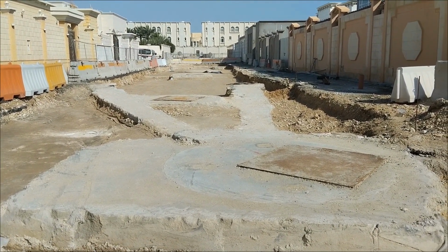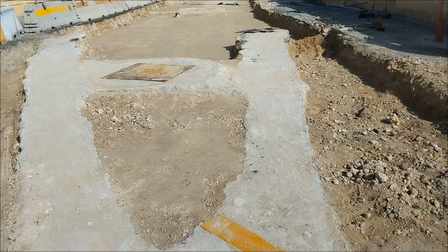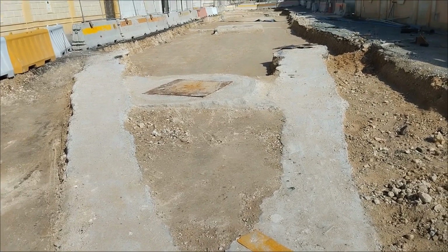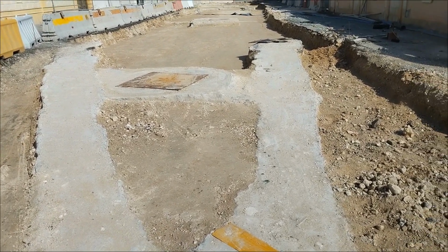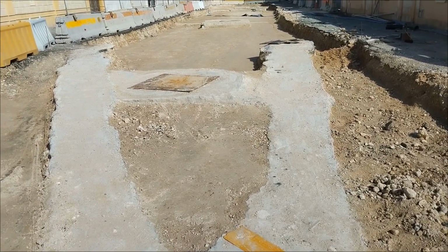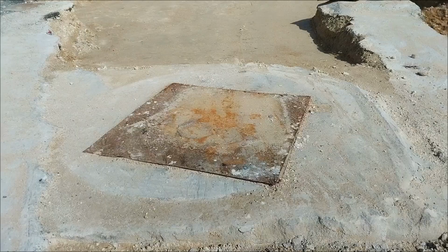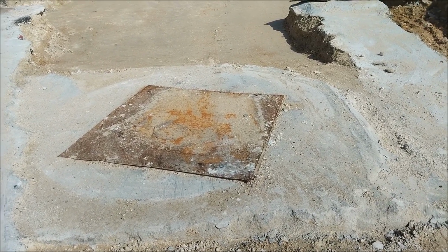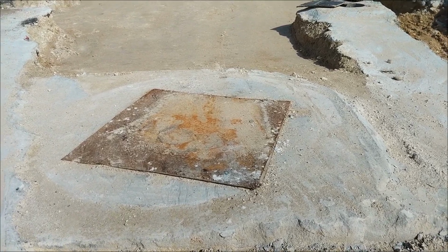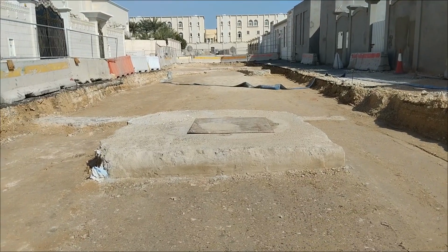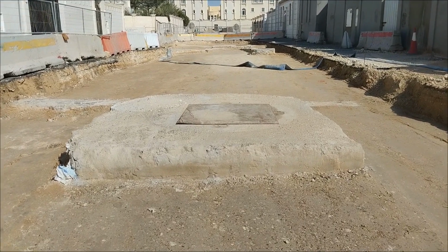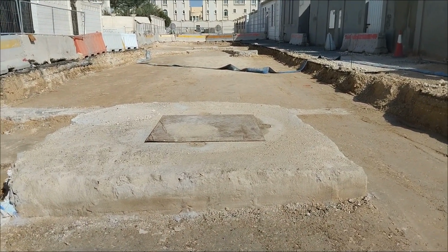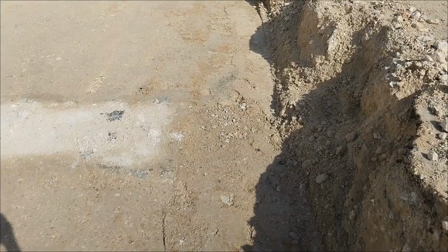I will show you the duct in this area now, where the duct bank concrete should be at the minimum at the subgrade top level, and should not be raised more than the subgrade top level. Any concrete should not be raised into the pavement structure. As you can see here, this is one manhole. The manhole concrete slab should be at the bottom of the subgrade or at least on the top of the subgrade.